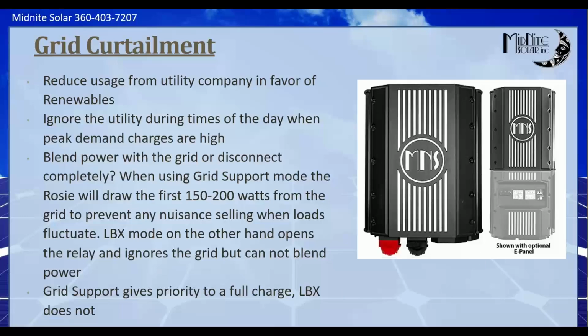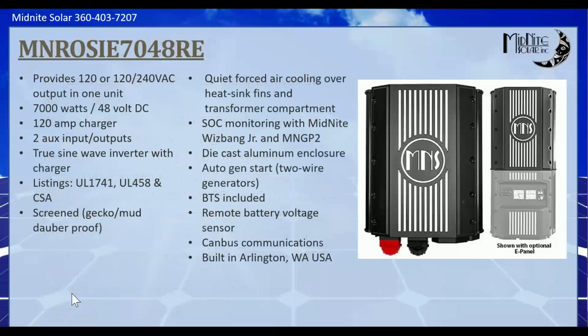So we'll jump through some specs, and then we're going to dive right into these modes. Most of you probably know these already, but I'll try not to put you to sleep while we talk about this. The Rosie is 120, 120/240, 120/208, 2 legs of 3-phase, 230 volts, 50 hertz, any of those options in a single inverter. So you can go into software, you can tell it you want it to be 120/208, or you can tell it, hey, I want you to be 230, 50 hertz because we're going somewhere else.